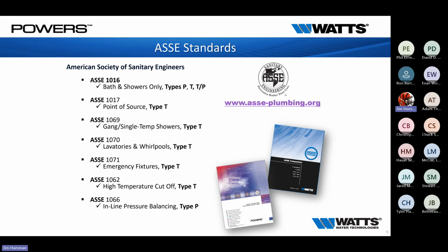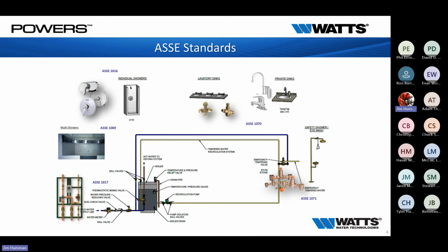If you get into extremely cold water, you won't be able to hold your face underneath it. Very hot, same thing. So it's very important that with this entire family of mixing valves, we get everything aligned exactly the way it is. I laid this out showing the entire family: we have our 1017 master mixing valve, which feeds our entire building, but then we're able to jump up into our showers, over to our labs, and really dial our entire system in to hit all those required temperatures for each individual fixture.